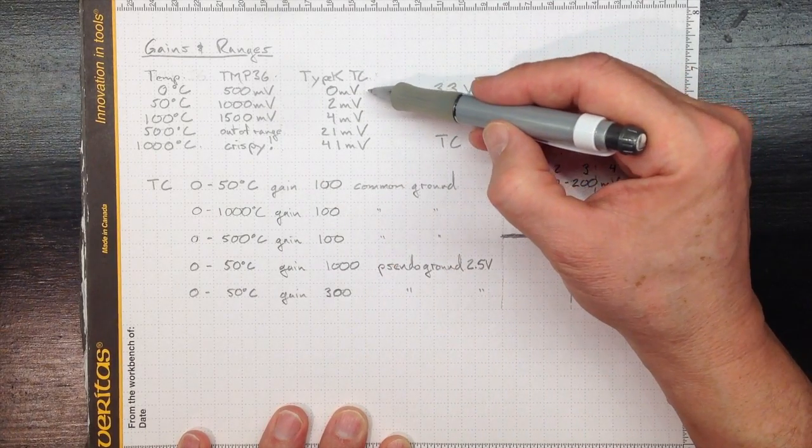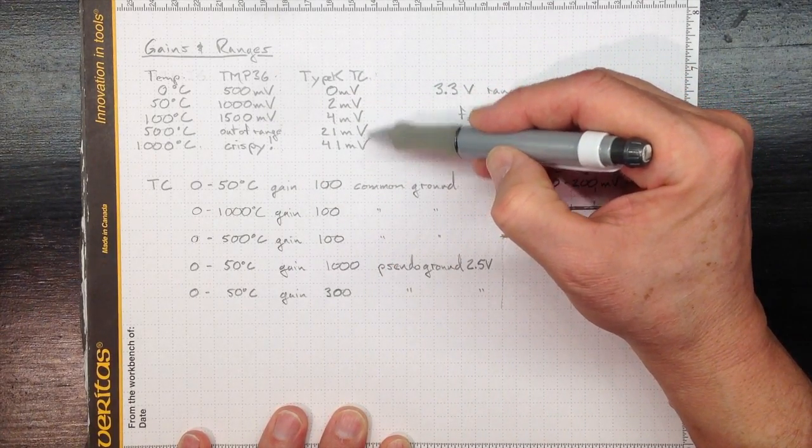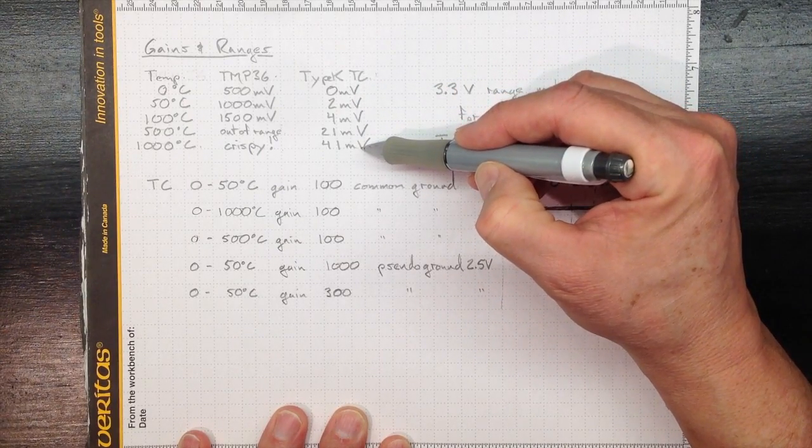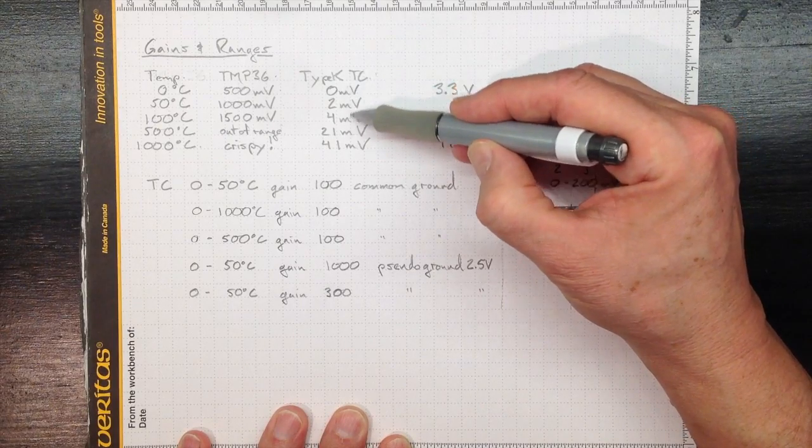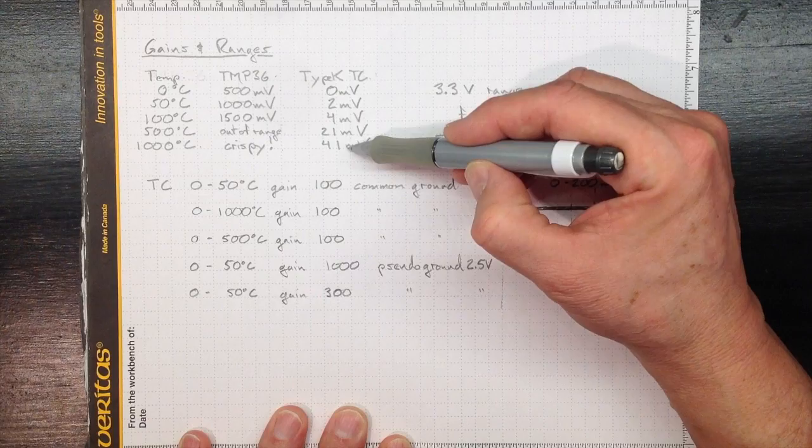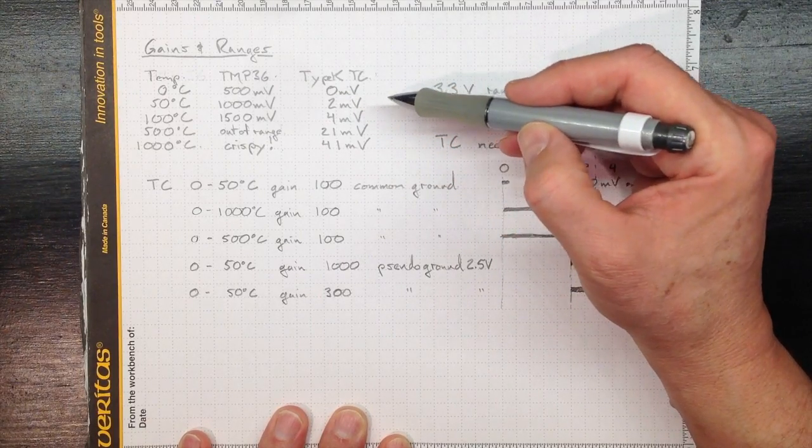A type K thermocouple gives us a much lower voltage output going from zero up to about 41 millivolts over that thousand degrees Celsius range. Depending on where we're trying to measure in that range, down in the low temperatures or up to higher temperatures, we'll choose different input ranges and gains.